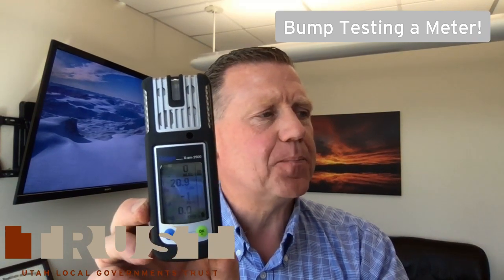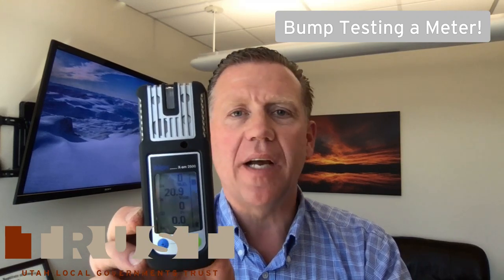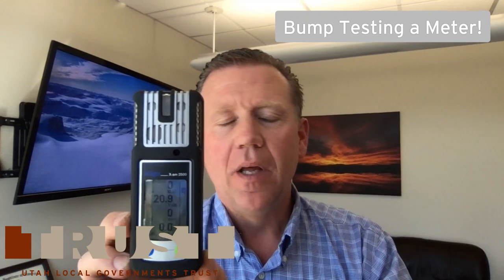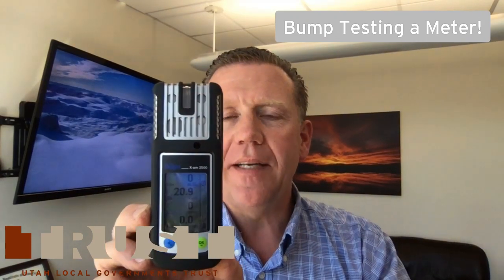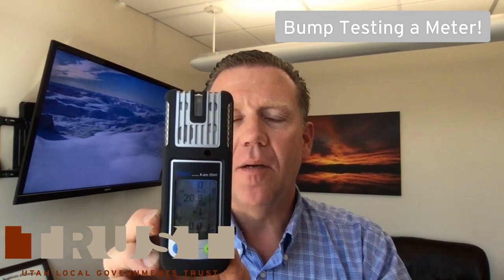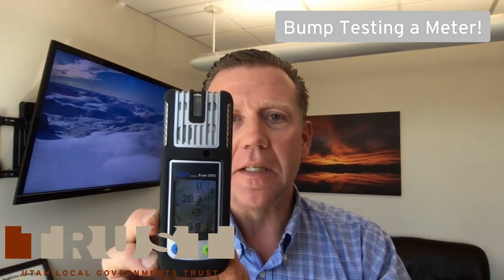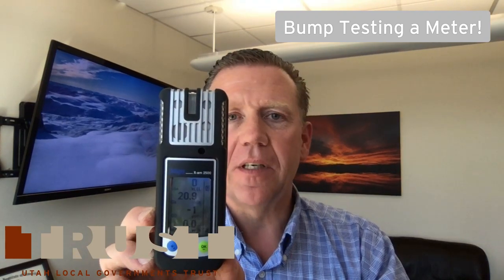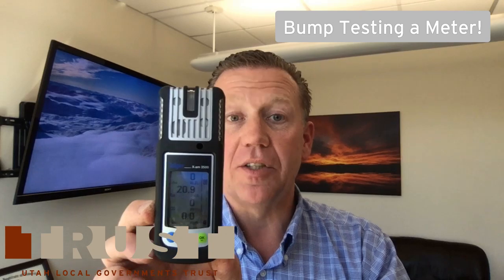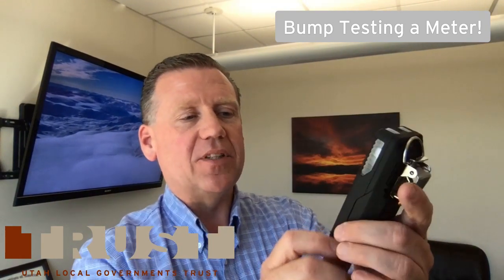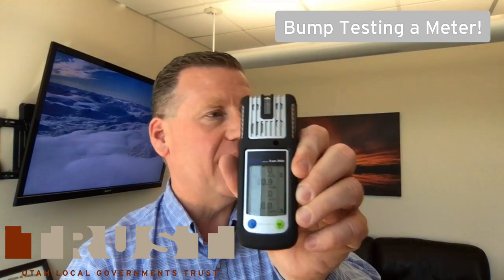Look at that number on carbon monoxide, it's moving, it goes from -2 to 0. Well, that means when I did my 0 calibration, I must have been in a little bit of dirty air, and so that's something I'll want to do that 0 again and reset that. But let's go ahead and do our bump test.